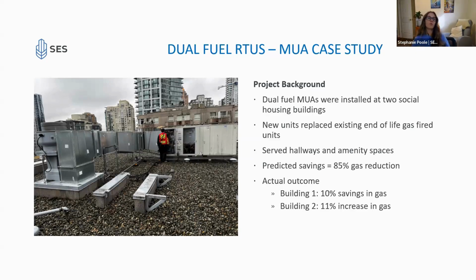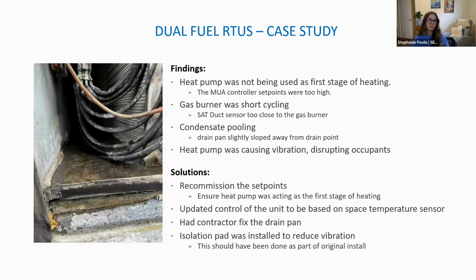So these buildings, again, were modeled to save, let's say, 50% of the gas. But in practice, we're seeing a 10% savings in one and actually an 11% increase in gas in the other building. You might look at this and be like, wow, they really messed that up. That's really unfortunate. But this is the norm that we're seeing: these are not performing as well as they are predicted to perform because the commissioning is not really being considered or not being done at all. That's why I really want to highlight this, because rooftop units have this potential, but we're not seeing it in practice. So you can go to the next slide.